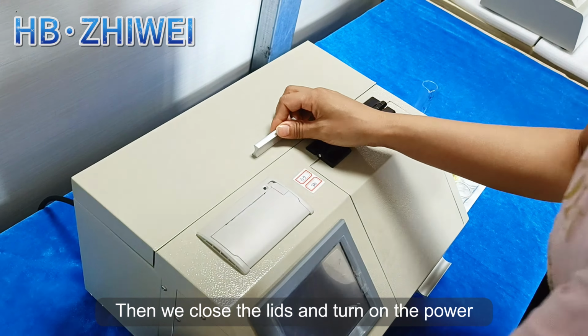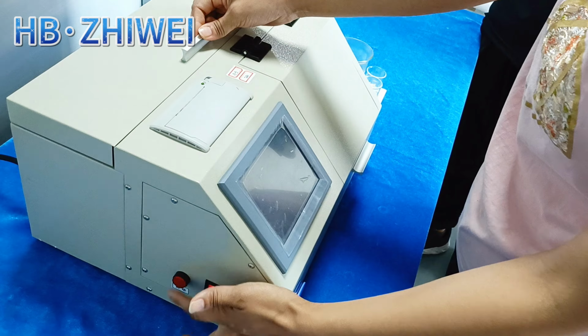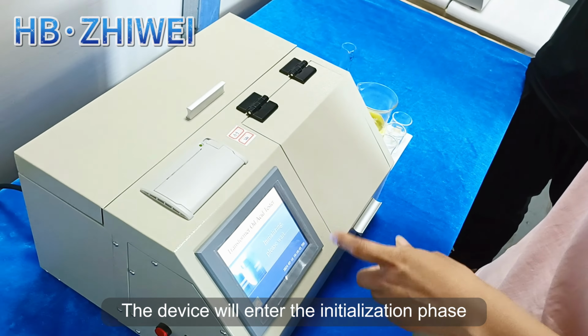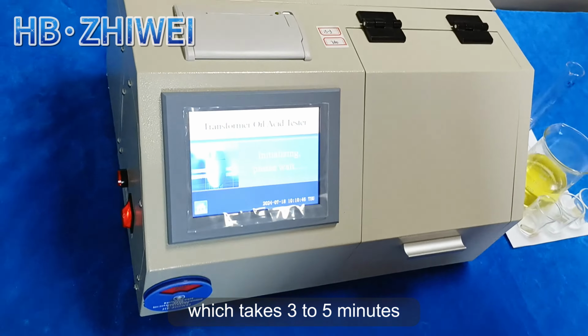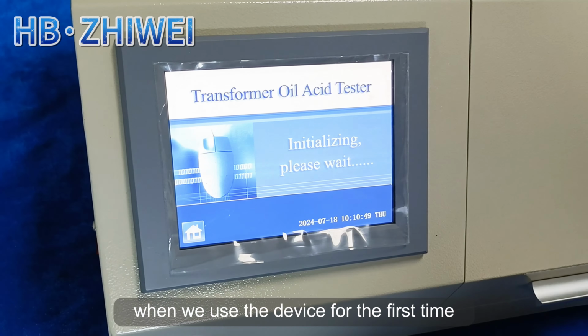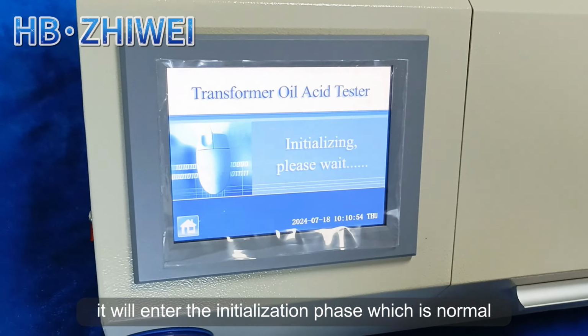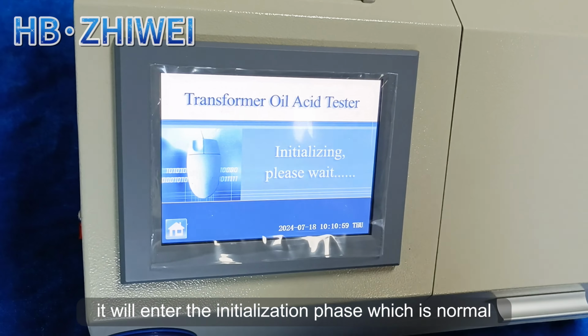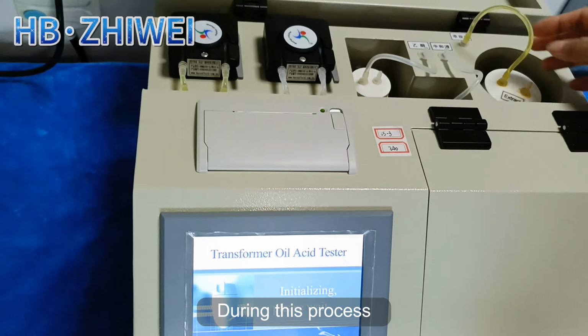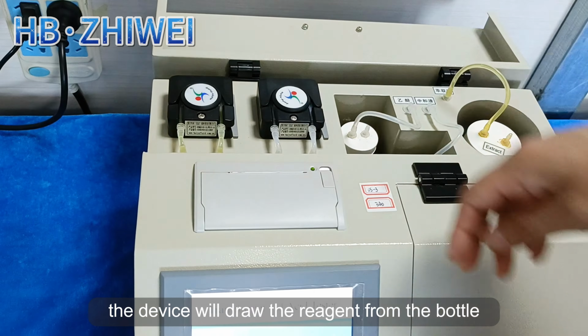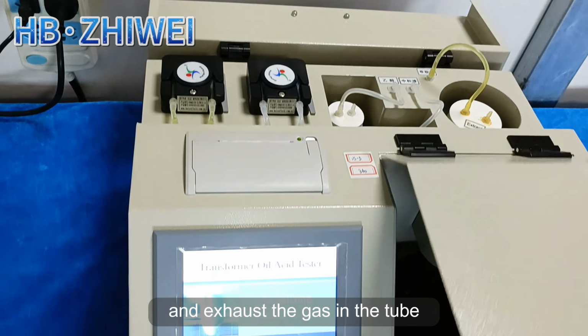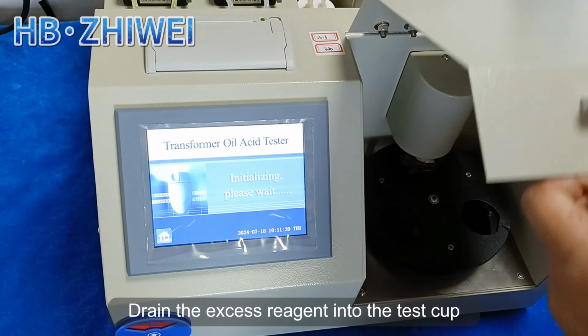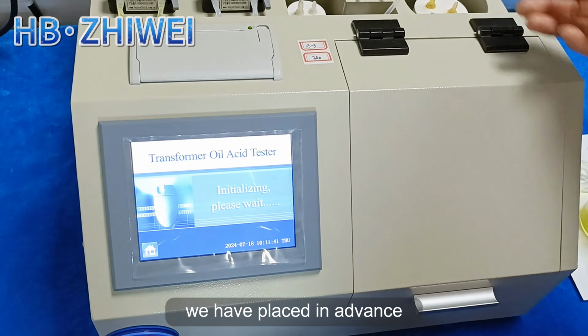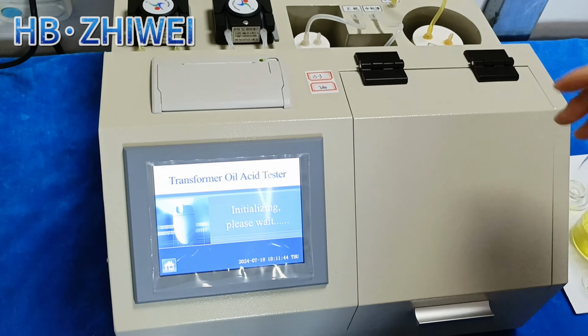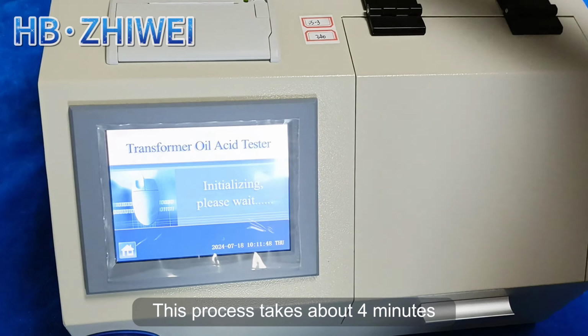Then we close the lids and turn on the power of the device. At this time, the device will enter the initialization phase, which takes 3 to 5 minutes. When we use the device for the first time, it will enter the initialization phase, which is normal. During this process, the device will draw the reagent from the bottle and exhaust the gas in the tube. Drain the excess reagent into the test cup we have placed in advance. This process takes about 4 minutes.